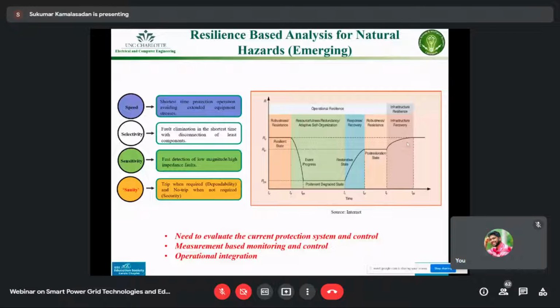In all these, the four main attributes are: speed, the shortest time for equipment to be taken care of, coming in or out, avoiding extended equipment stress; selectivity, elimination of the bad part of the system, how fast you can do that; sensitivity, fast detection of low and high magnitude faults on the power grid; and sanity, the dependability of the system, making sure you can depend on it at all times so that the minimum part of the system is isolated.